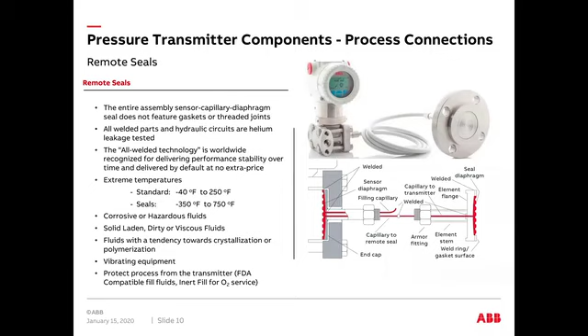Another thing to talk about in this heart of the transmitter is the transducer itself. So there's a wide range of pressures, and when you look at a specification sheet or what you want to choose for your transmitter, you can have process pressure, which is typically what you're talking about, but you also may need to pay attention to the overpressure. You won't be getting the reading, but you won't damage the sensor. It'll come back down and still be operational. And there's a burst pressure, which for safety wise, you need to know to make sure there's not going to be any kind of a break in and leaking of the process.